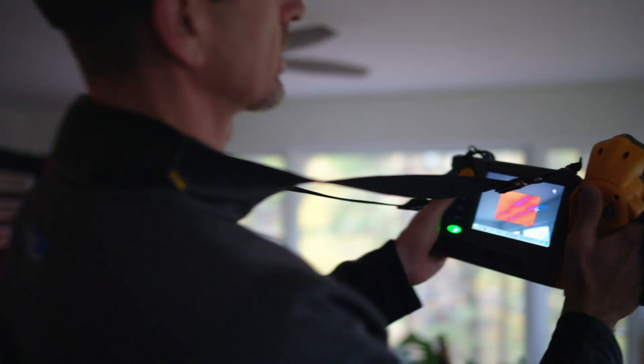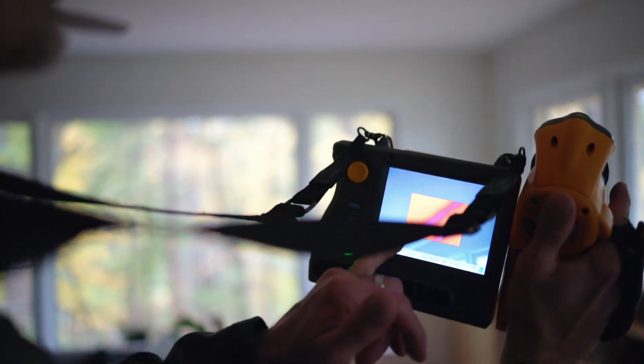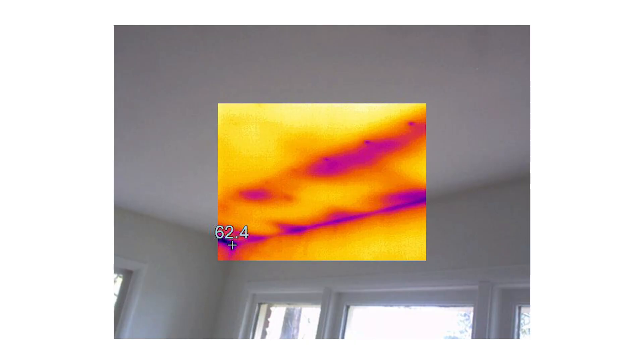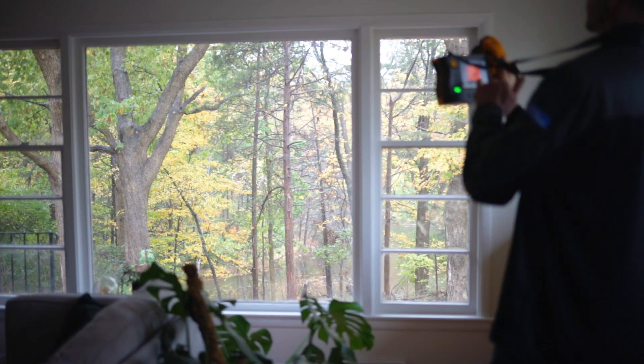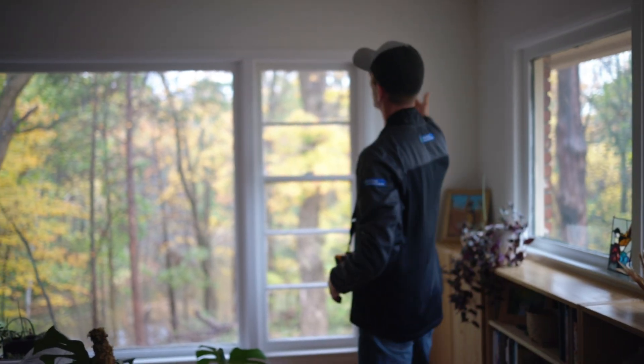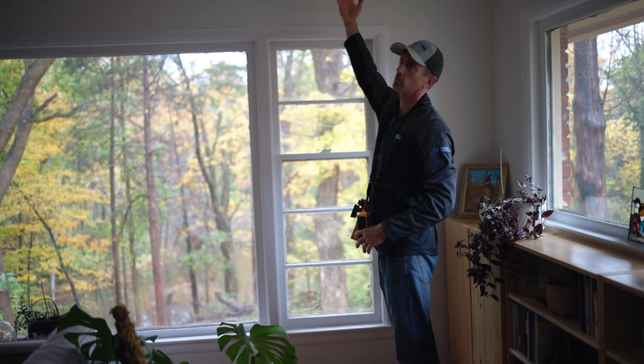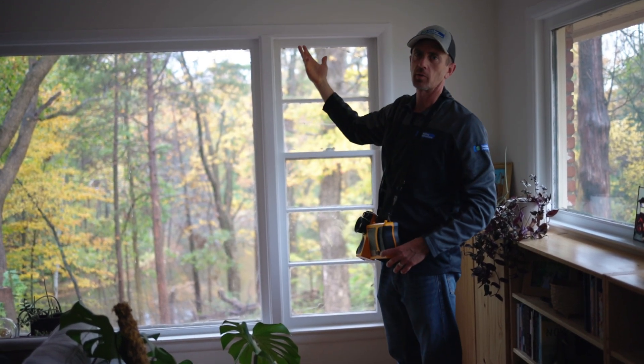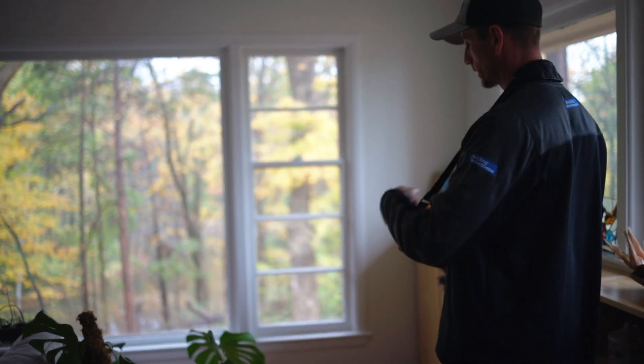Some things that really surprised me. Here you can actually see the ceiling is missing insulation as well. There's a ceiling joist right here — that's the last ceiling joist above the top plate of the exterior wall. When you get a big gust of wind outside, the air will come through the soffit and push the insulation away from the edge of the ceiling, leaving basically uninsulated parts of your ceiling along the edge of the outside wall.